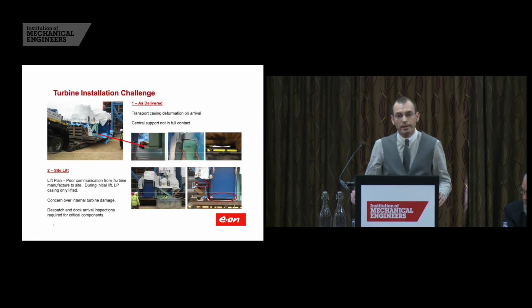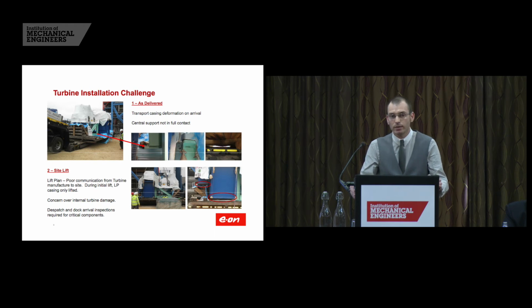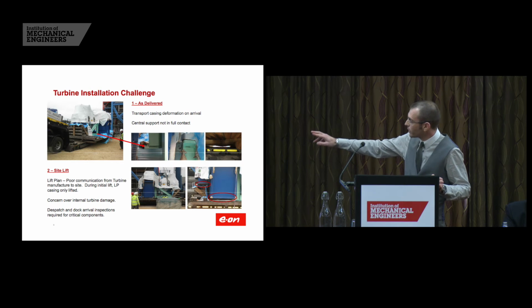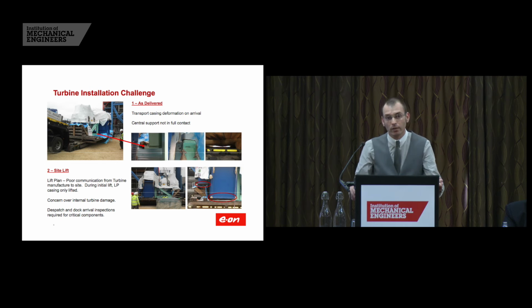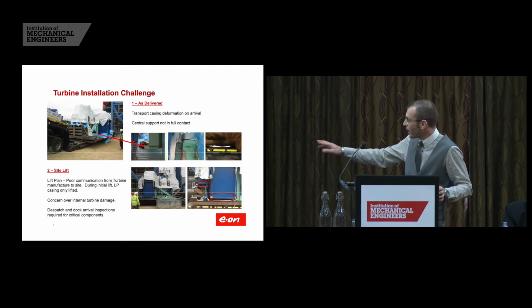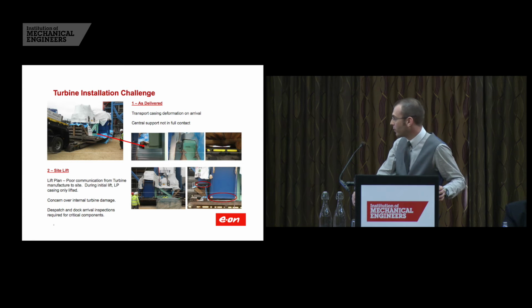Right, the first major challenge to present the contract was actually on day 1 of arrival of the steam turbine. On investigation of the transport, when it arrived into site, it was noted that the support structure that held the turbine, you see the support structure here in green, was not actually in contact with the steam turbine. On a closer investigation, we could see that this was down to the wooden support frame itself. It got wet and it bowed.